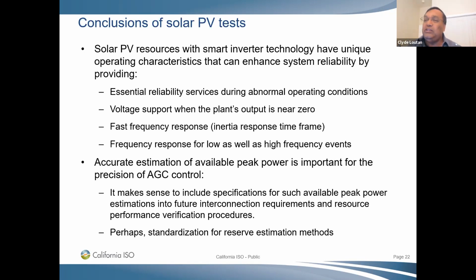So in other words, within the US on the grid, we do not operate to control a power factor. We operate to control a scheduled voltage. On the 230 kV, let's say in the San Francisco area, the scheduled voltage there is 230 kV, and we allow that to move from 228 to 232. The power factor range on that unit could vary, as I said, between 0.95 lead and 0.95 lag, to try to maintain that voltage between 228 and 232.